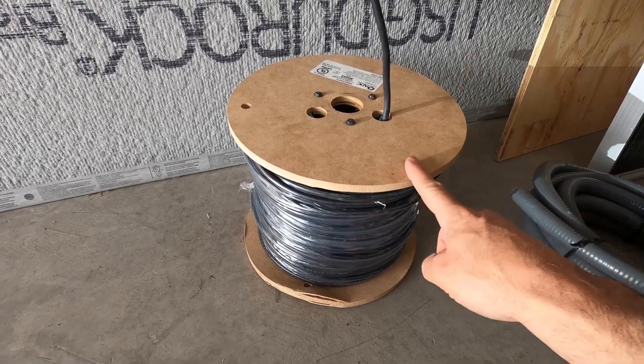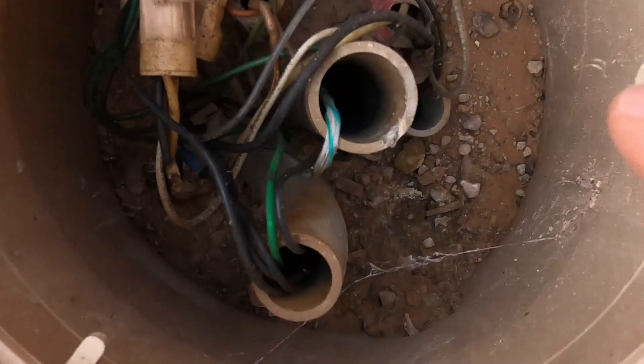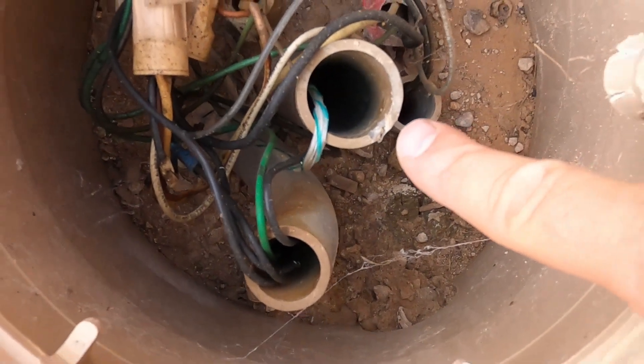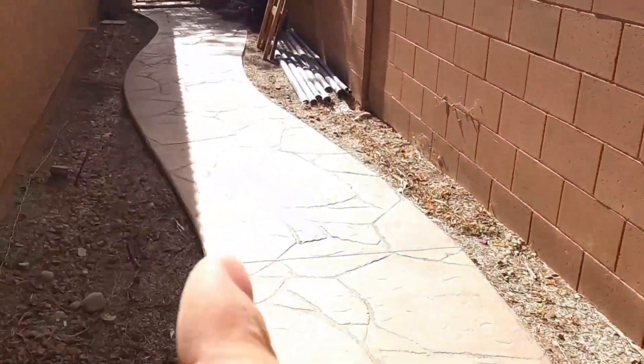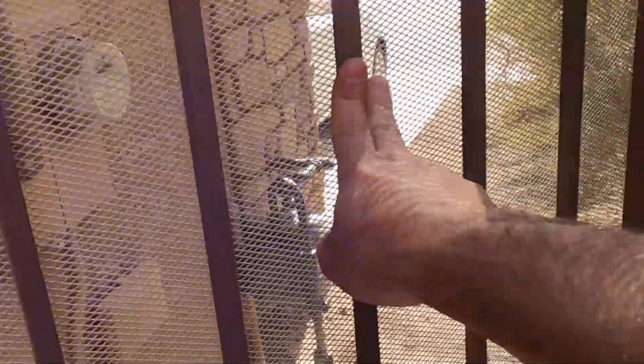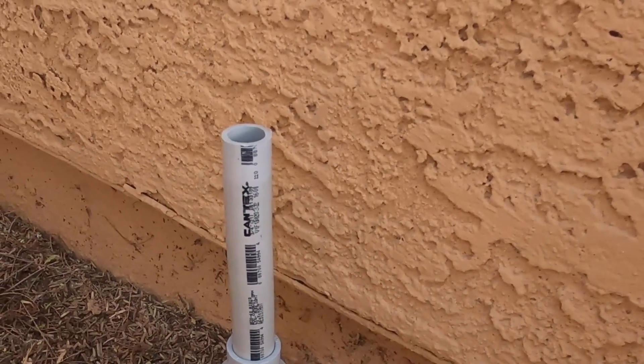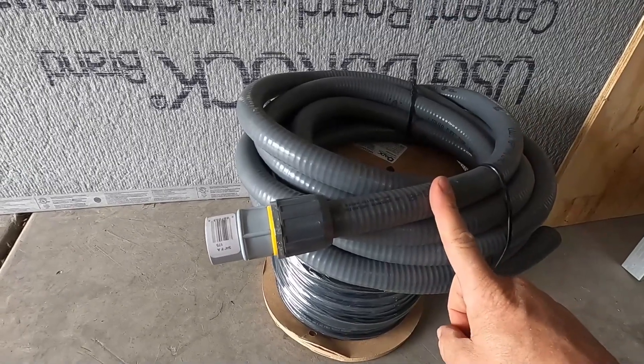Today we're going to be pulling some 8 gauge PV wire. We've got 500 feet of PV wire. We'll be running it from the test array through this one and a quarter inch conduit to the end of the conduit, about 120 feet, through the wall, and finally terminating through this liquid tight conduit.